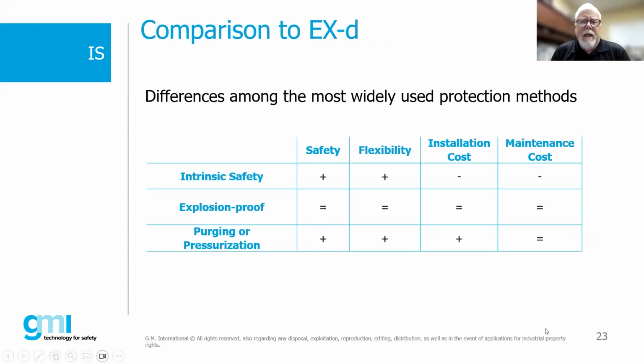So I think on the next slide, a little bit about the comparison of intrinsic safety versus, say for example, EXD. We won't spend too much time on this, but as Barbara mentioned, intrinsic safety is one of those protection concepts that is in the international world approved for zone 0, where flame proof is not approved for zone 0, but it is approved for zone 1.